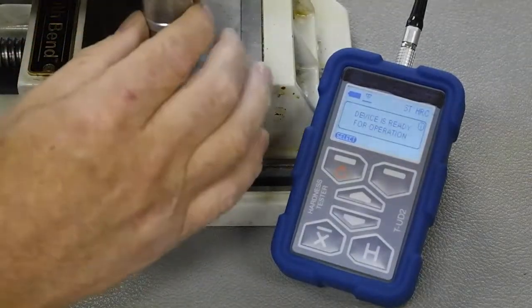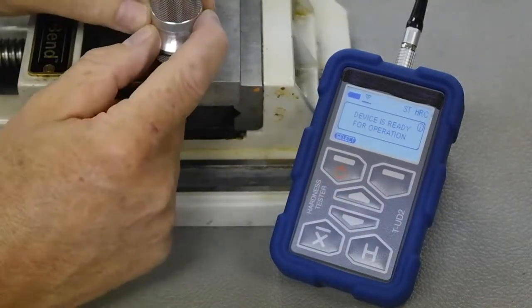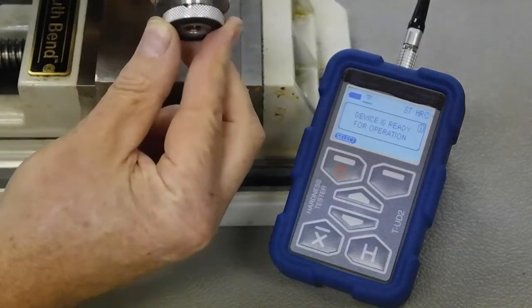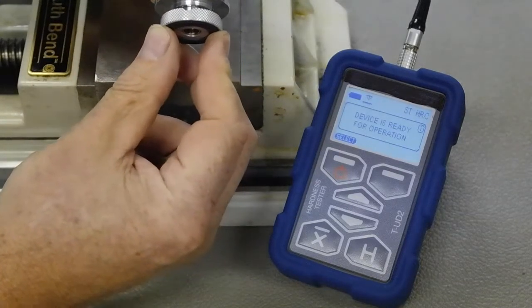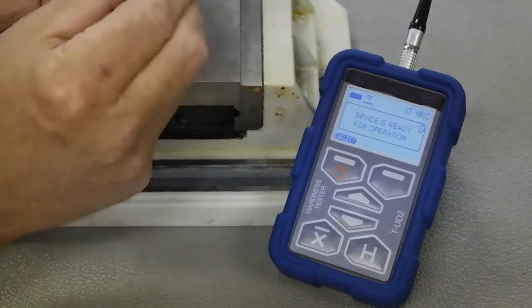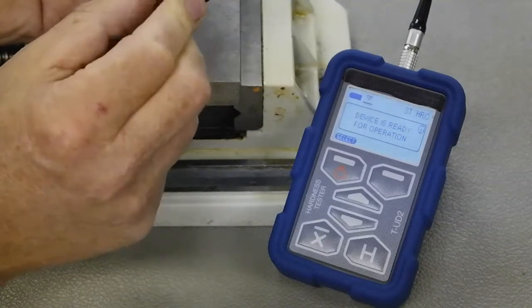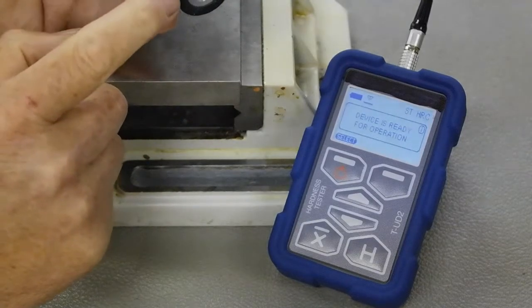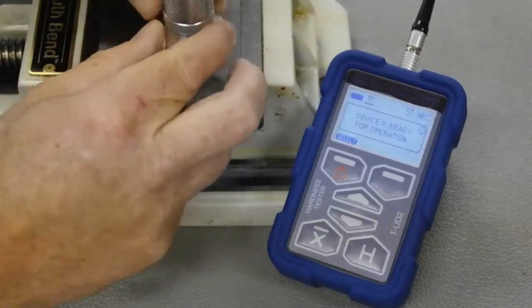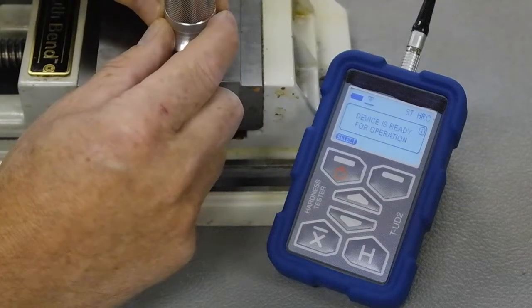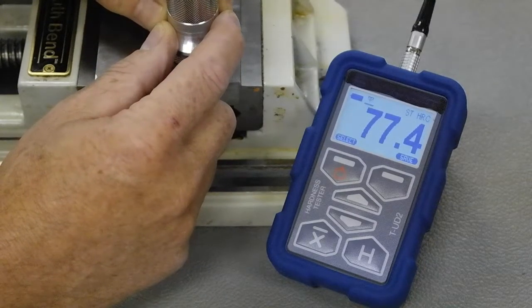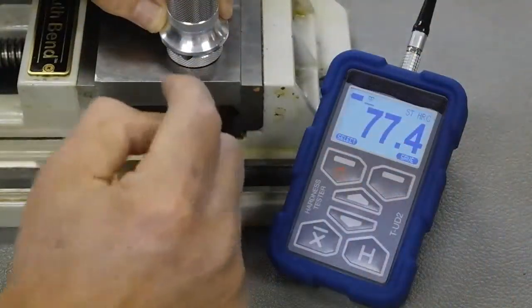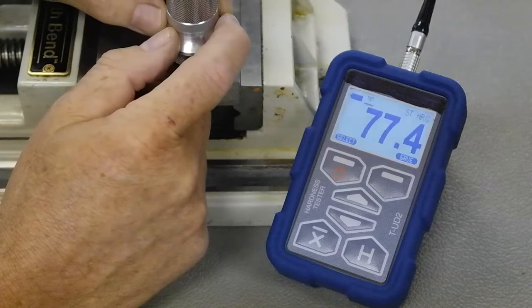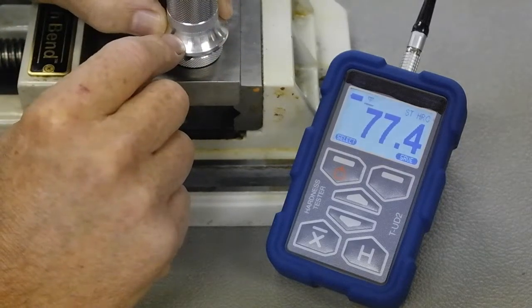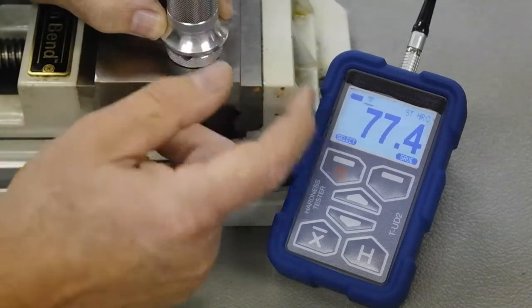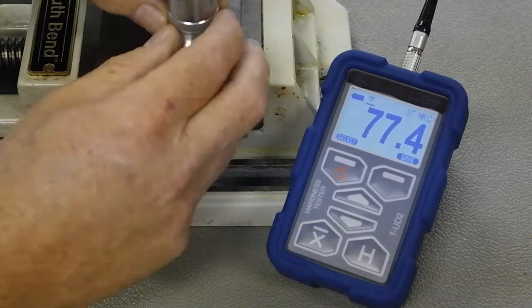But I'll just show you that if, when I'm doing a test, I push down, and it's a two-step process. So the first thing is the spring on the foot, it's taking up its load, and then once that is done, and then the tip is exposed, and we go deep enough, you can see here a secondary load which is pushing the rod with the diamond tip up inside of the probe. So when I press down, you'll see the icon will move on the screen. That means contact is made, and it's trying to do a test. All that's happened is the loop through the device has been closed. But because I haven't applied the correct load, in this case it's a 50 N probe, or approximately 12.5 pounds, 50 N is 50 newtons, it's got to take up that secondary load.